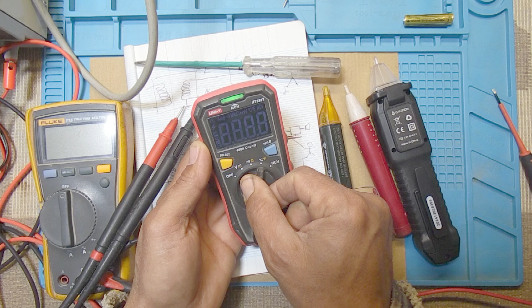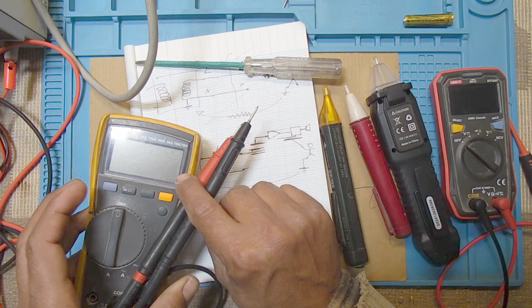So we have two types of voltage detectors: those that use direct contact, and those that use capacitive coupling. This function is now integrated in newer meters. For example, this UNI-T has NCV, non-contact voltage detection. We can see here it has a tiny paragraph about it. But always check live and neutral with a meter, it's safer, because those detectors can give you a false detection if you are not connected to the earth.